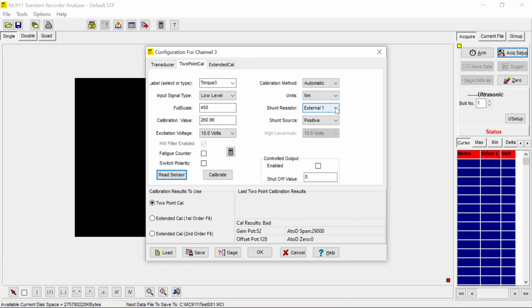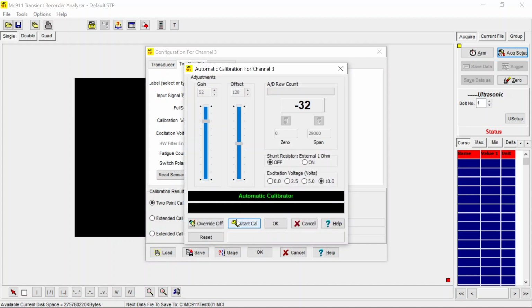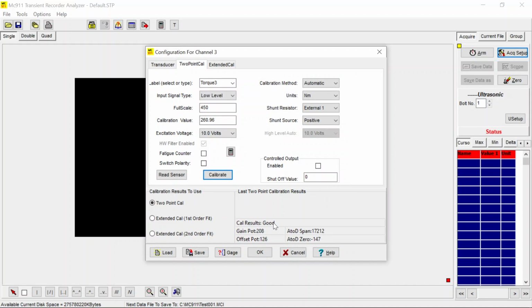The reason we use external one is that we want to use that 218.4K resistor. Internally, we only have two resistors, which doesn't satisfy that resistance. So we introduce it through the external one shunt resistor to accomplish this. So once we're done, we have calibrated both of them. In here, this is a normal 0.403 millivolt per volt for thread torque. So both of them are set to go and ready to acquire data.